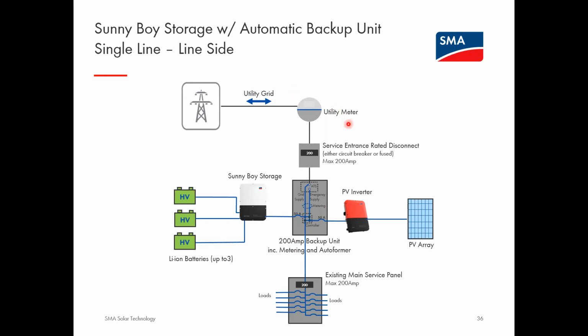In the event of a power failure, a grid outage, the automatic transfer switch here closes, and everything below it is able to be supplied by both the SunnyBoy Storage and the PV inverter, so your protected load panel becomes the existing main service panel inside of the home. This is nice for a couple of reasons. One, you completely avoid the 120% rule in the NEC by connecting both the PV and the SunnyBoy Storage on the line side of the main breaker.